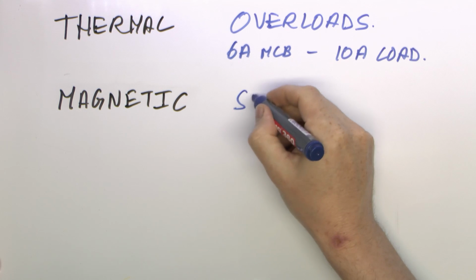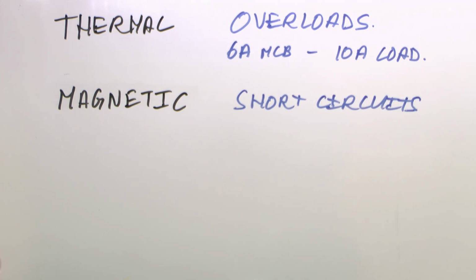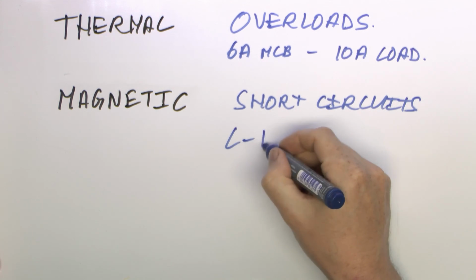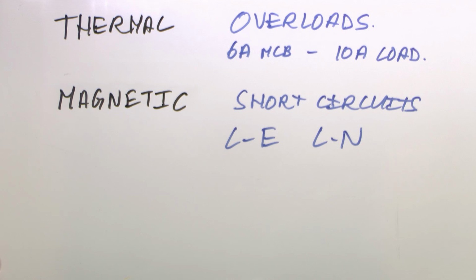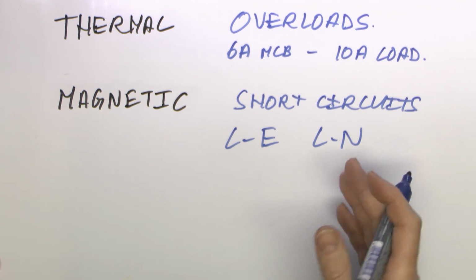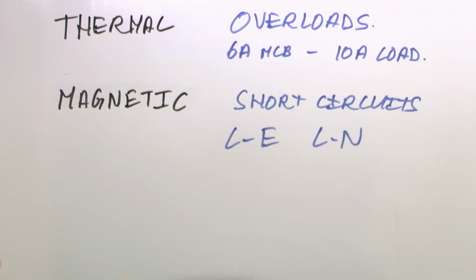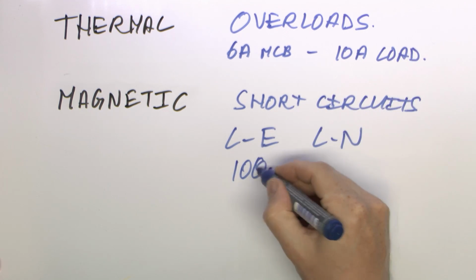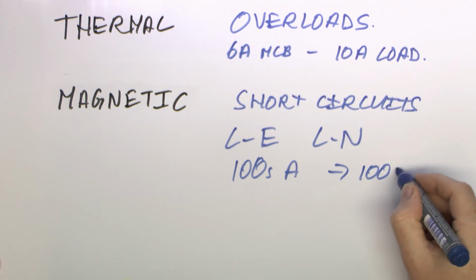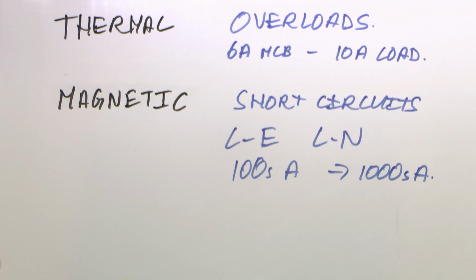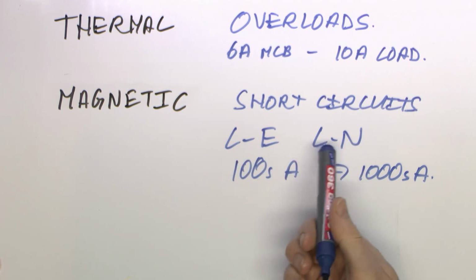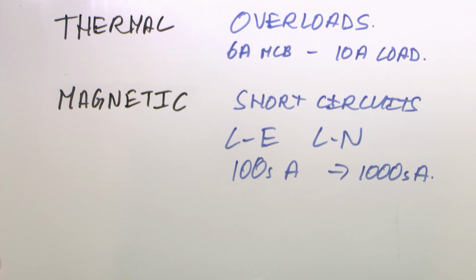Now, the magnetic part is for short circuits, and this is the kind of thing where you have a fault, say between line and earth, or between line and neutral, and the result in this case is that the current that will flow is going to be significantly higher than you're going to get in some sort of overload situation. Typically it could be in the order of hundreds of amps, or in some cases many thousands of amps. Because basically you're putting a wire directly between two of these things, and the current is going to be limited by the impedance of the circuit, which in most cases is going to be very small, in the order of only a few ohms or even less than 1 ohm. And this part is designed to react very quickly, not quite instantly, but pretty much as near as you can get.